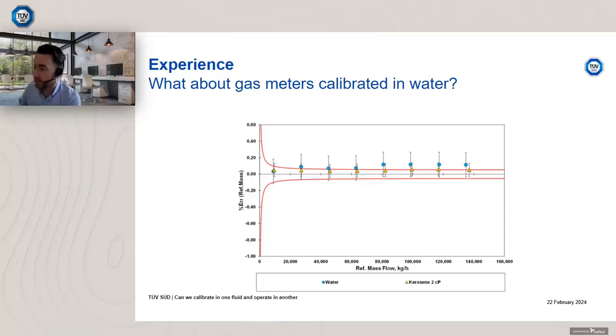So what about gas meters calibrated in water? If we go back, I have two fluids here. I have water and I also have kerosene. So blue data points being water, and I've included the uncertainty bars because it's quite important to show you there's a different uncertainty between our facilities, and certainly for gas, where gas uncertainty becomes greater. So this is for liquid. Again, just to describe the chart, on the x-axis I've got reference mass flow in kilograms per hour, and on the y-axis I've got percentage error.